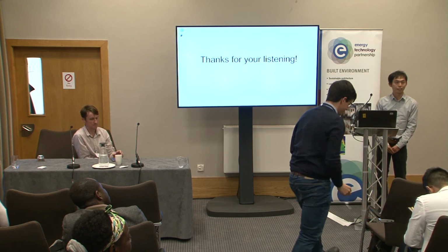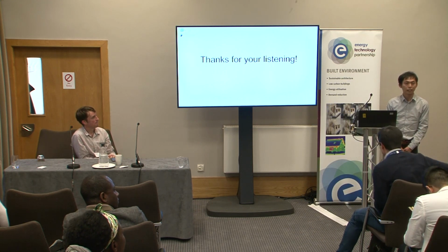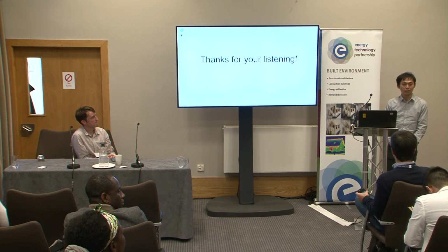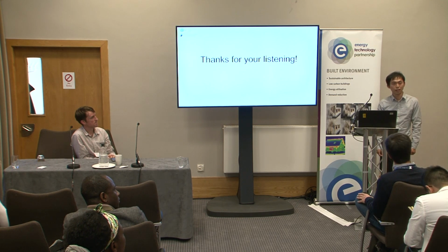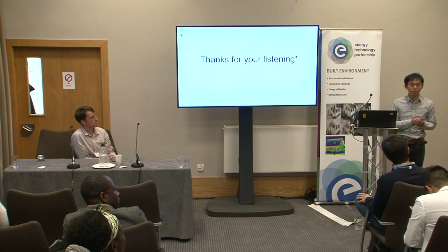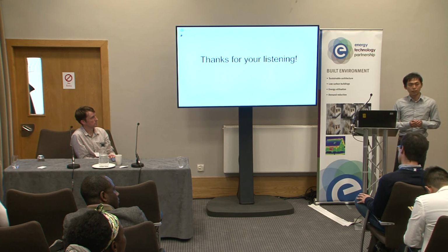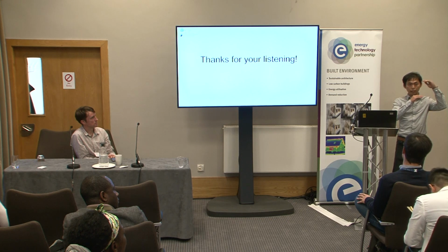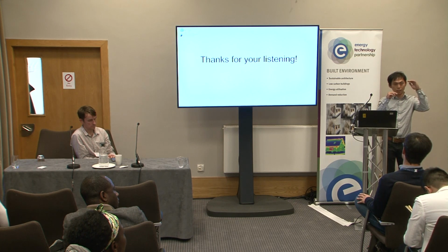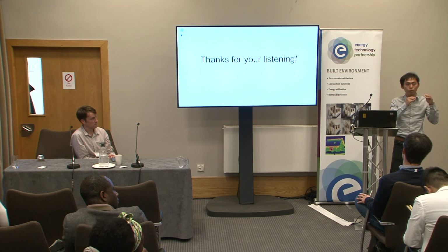So will this reduce energy consumption in the library? Yes. The storage room in a National Library is a little bit different from comfort air conditioning, because they focus on accuracy control. For example, for daily control, they set a control band for temperature of 15 to 20 centigrade, and for RH 50% to 60%. Also, they have requirements for daily fluctuation.